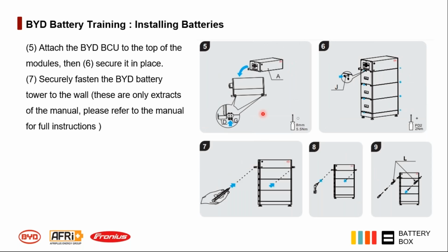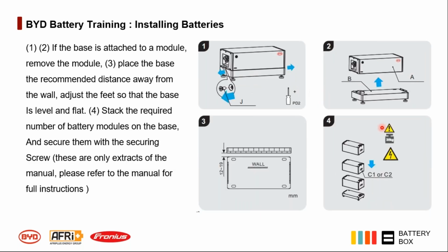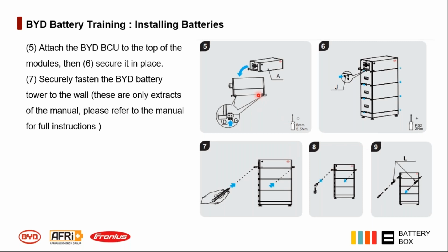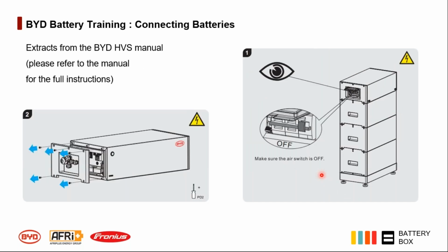And then when attaching your modules, they're stacked pretty much like Lego. They're giant Lego blocks. Then it's important to mount your top box to the wall, just to ensure that your battery doesn't tip over and is quite secure. Here we've got the connection area. All the connections to your inverter happen in that area, and on the other side you've got your breaker, that side of the top box.